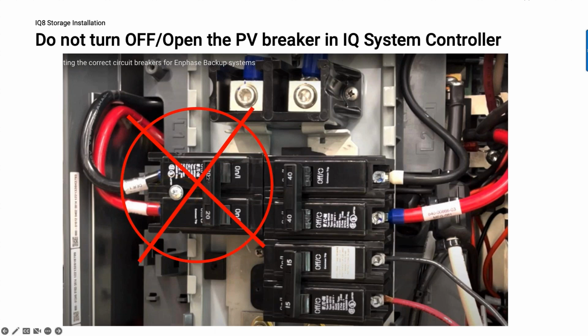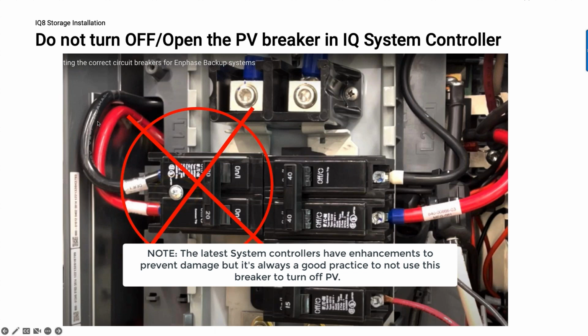So remember, this breaker is an overcurrent protection breaker. So if you have a short across these lines that creates an overcurrent situation, and this trips, likely what's going to happen is if the microinverters detect that there's a short between these lines, the microinverters actually will stop producing. So the microinverters will stop producing, this will trip, but because the microinverters are not producing, we don't have any power that's actually going to damage the system controller. The situation here is that if you manually flip this switch off when the microinverters are producing power, then that will be the dynamic that kind of creates that problem.